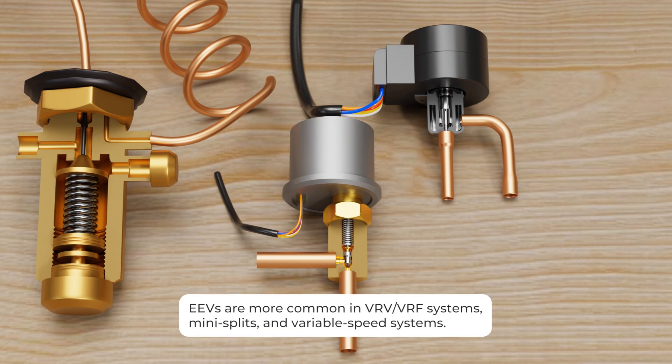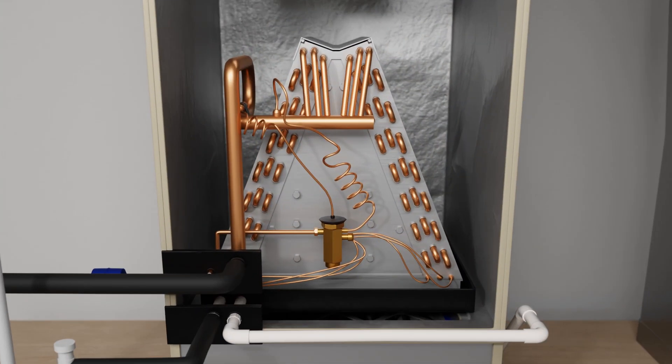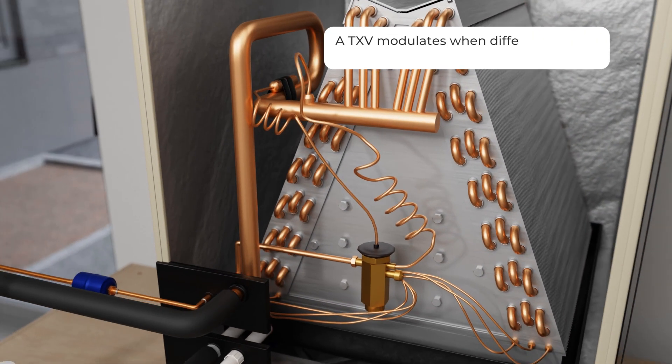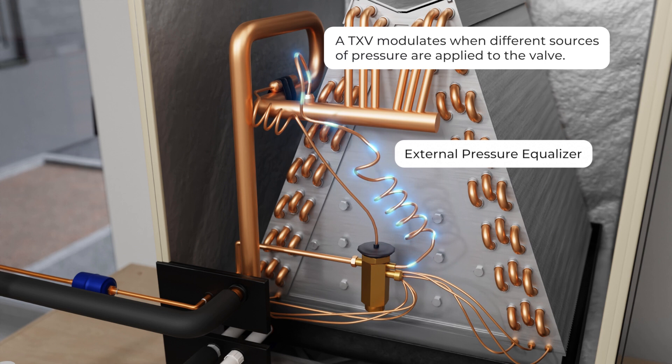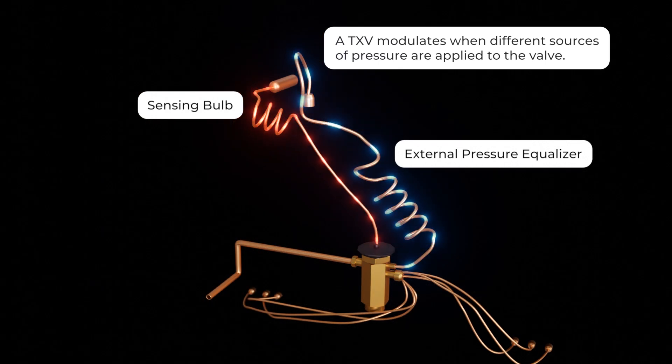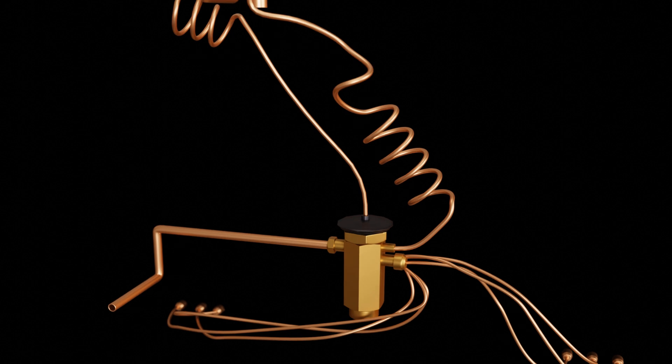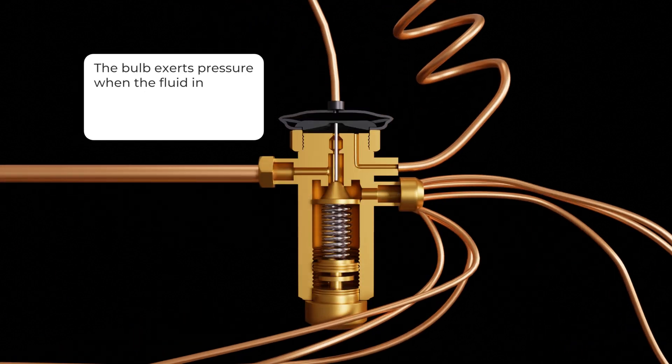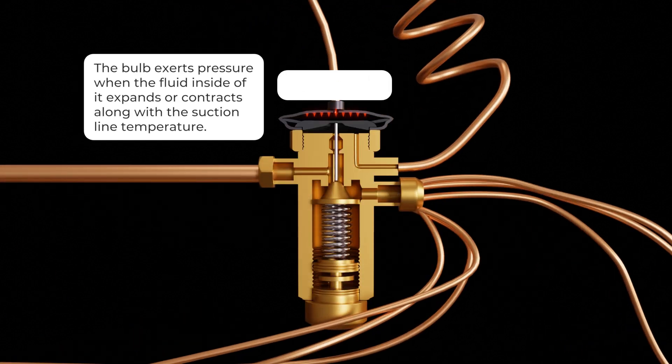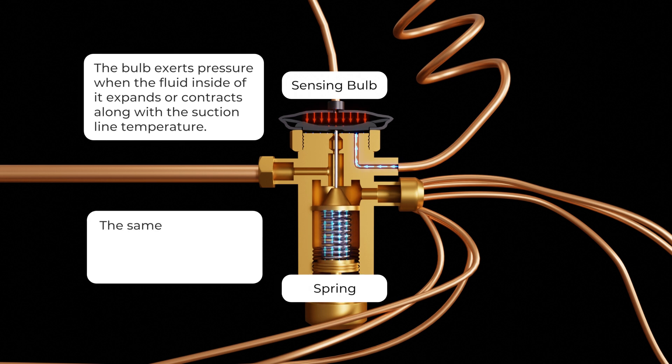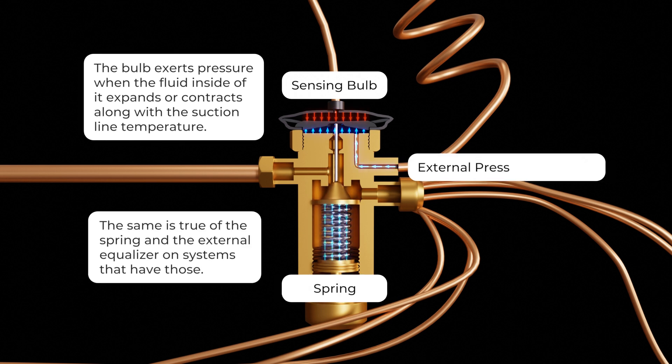They're more common in VRV or VRF systems, mini splits, and variable speed systems. A TXV is a mechanical device that modulates when different sources of pressure are applied to the valve. The bulb exerts pressure when the fluid inside of it expands or contracts along with the suction line temperature. The same is true of the spring and the external equalizer on systems that have those.